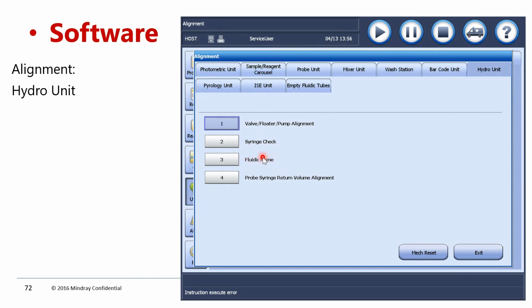Fluidic prime, at the time of installation we used to do fluidic prime. Probe syringe return volume alignment. We need to adjust this whenever the probe syringe is dispensing the wash water. Again, it will pull back some water, not completely, but it will pull back, so as not to have dripping on the wash station. Means it will push the water, and it will pull a little bit backward so as not to drip on the cuvettes or any other place. That volume alignment also we can do.